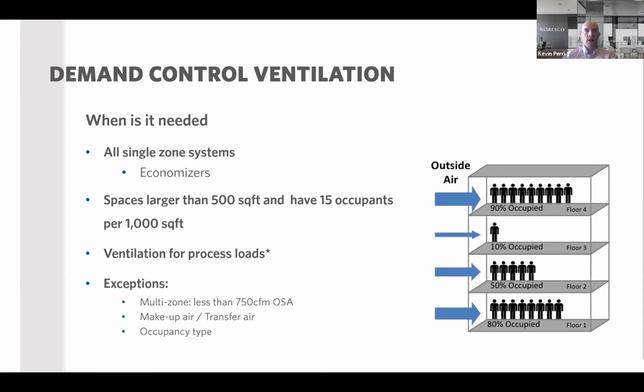So if you fall into either of these categories and you need demand control ventilation, they have some exceptions here. If you have a multi-zone system that's less than 750 CFM of outside air, then you're exempt from demand control ventilation. That 750 CFM used to be 1,200 CFM. So they're tightening the belt a little bit there. If you have makeup air or transfer air systems, that would be an exception for not needing demand control ventilation if that's what your equipment is used for.